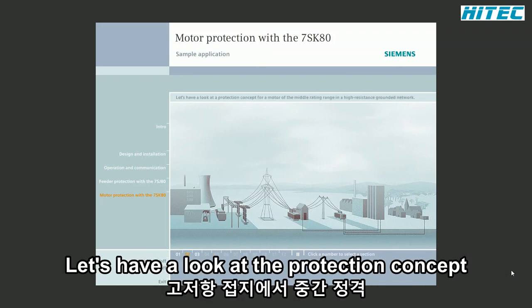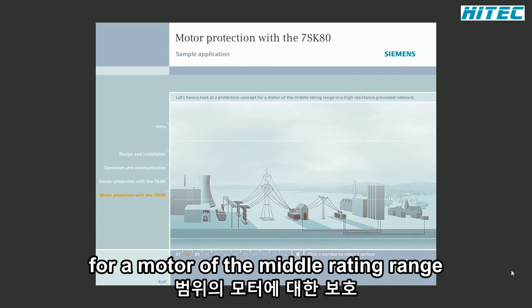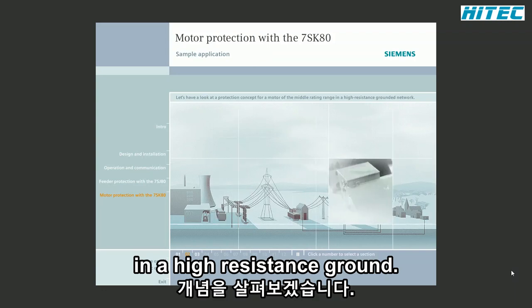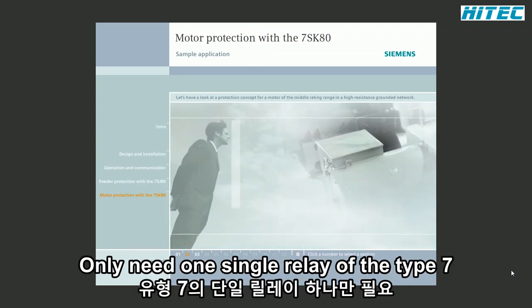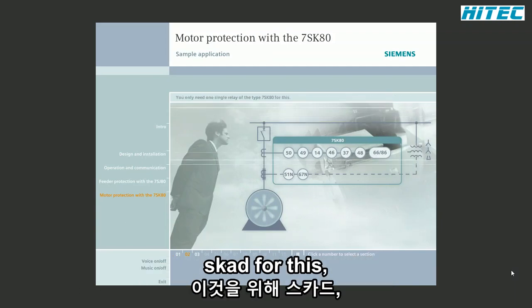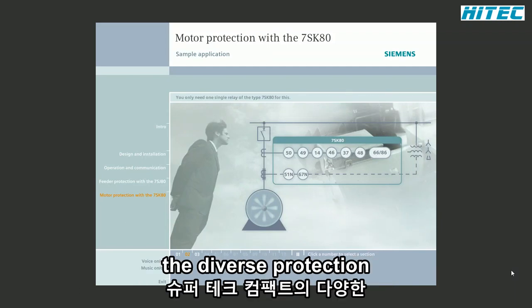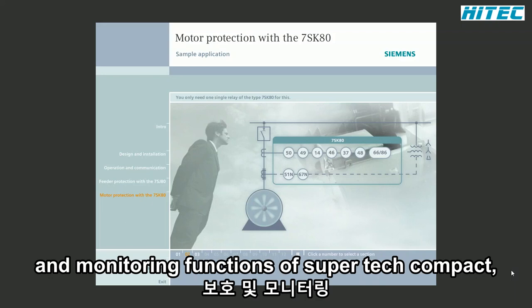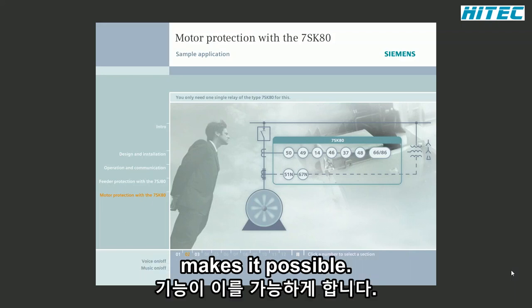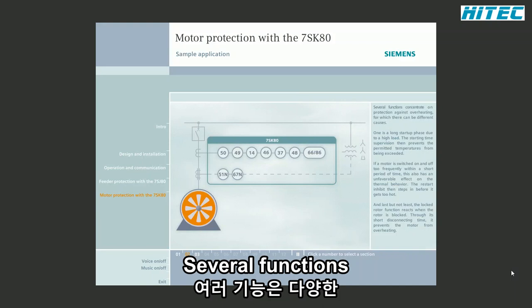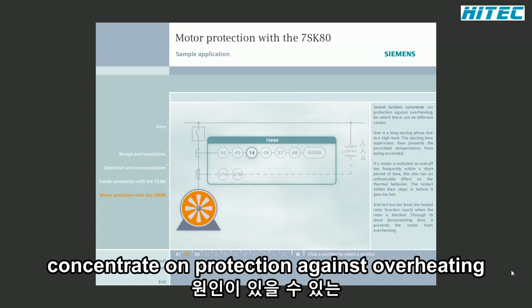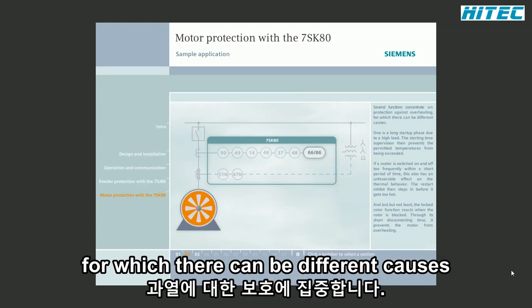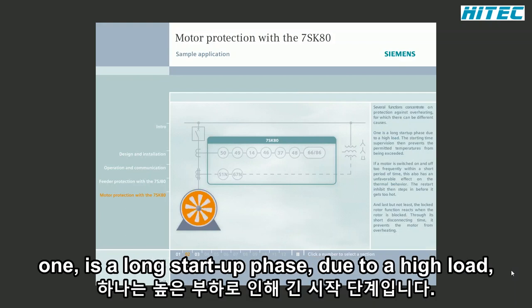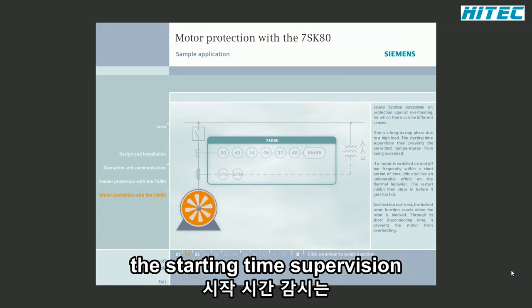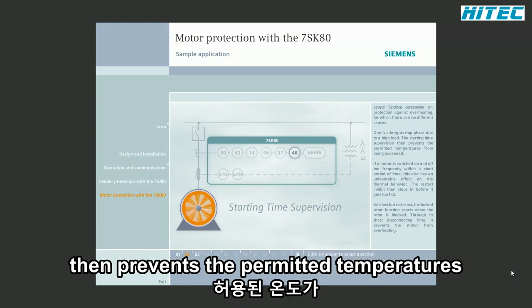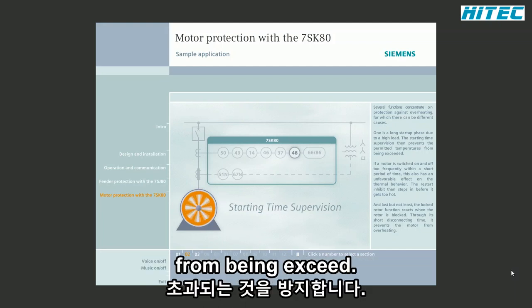Let's have a look at the protection concept for a motor of the middle rating range in a high-resistance grounded network. You only need one single relay of the type 7SK80 for this. The diverse protection and monitoring functions of SIPROTEC Compact make it possible. Several functions concentrate on protection against overheating, for which there can be different causes. One is a long startup phase due to a high load. The starting time supervision then prevents the permitted temperatures from being exceeded.